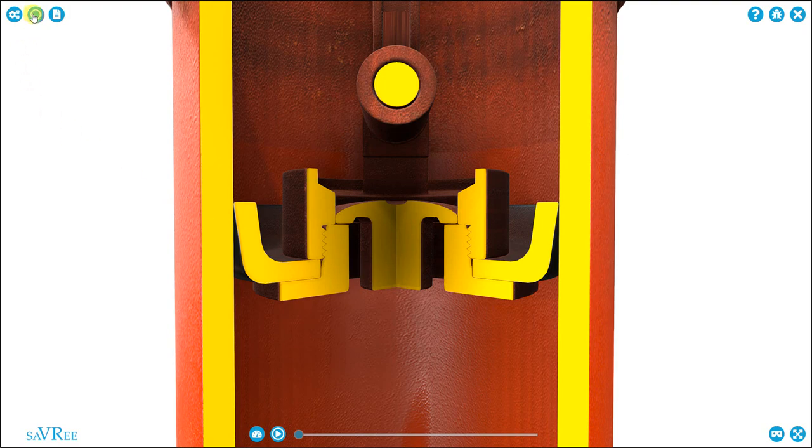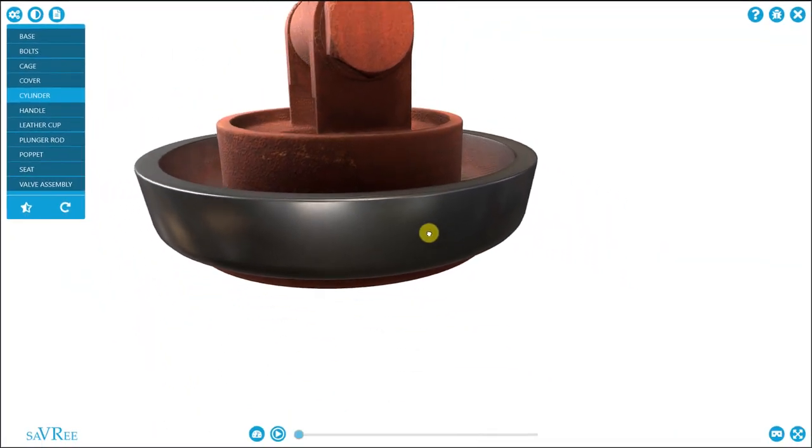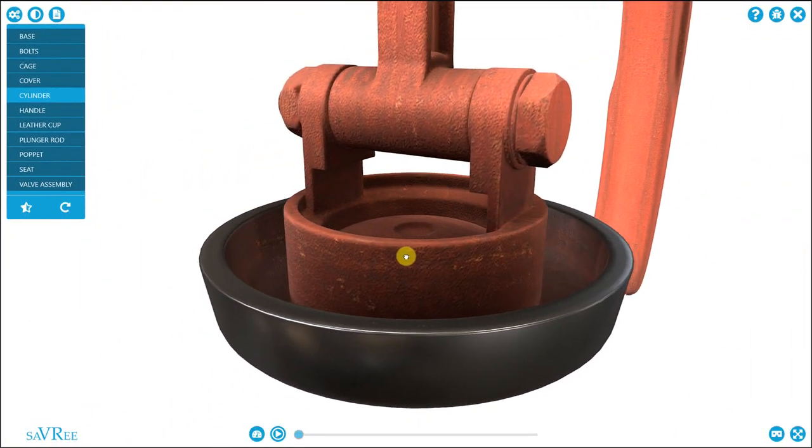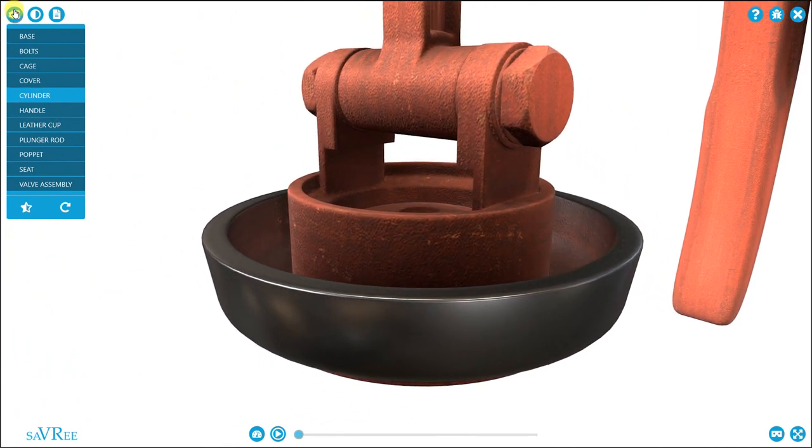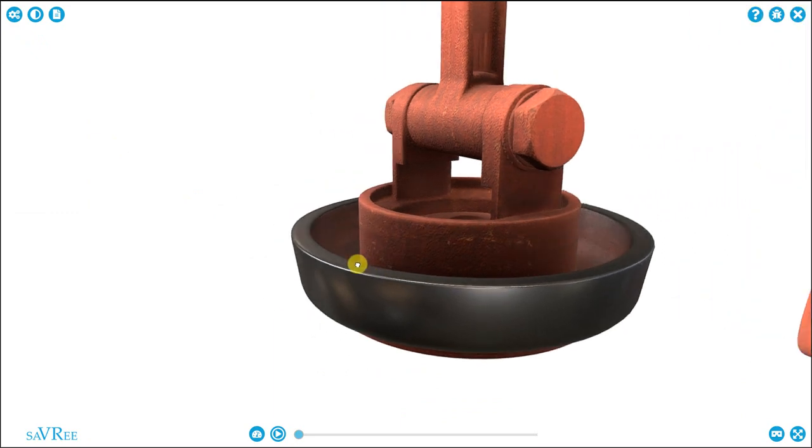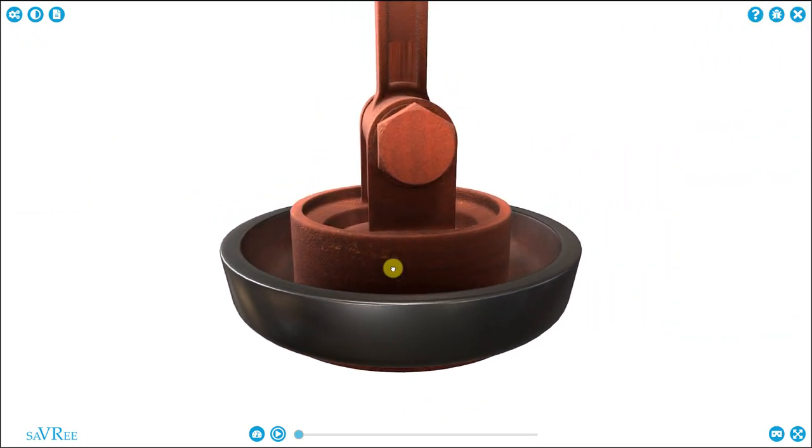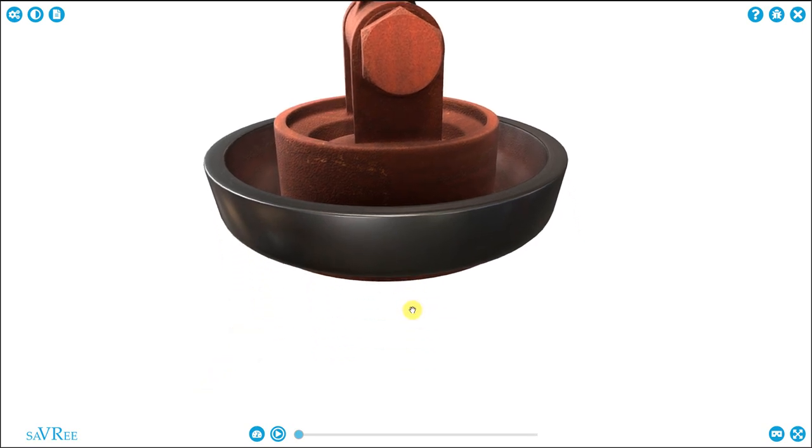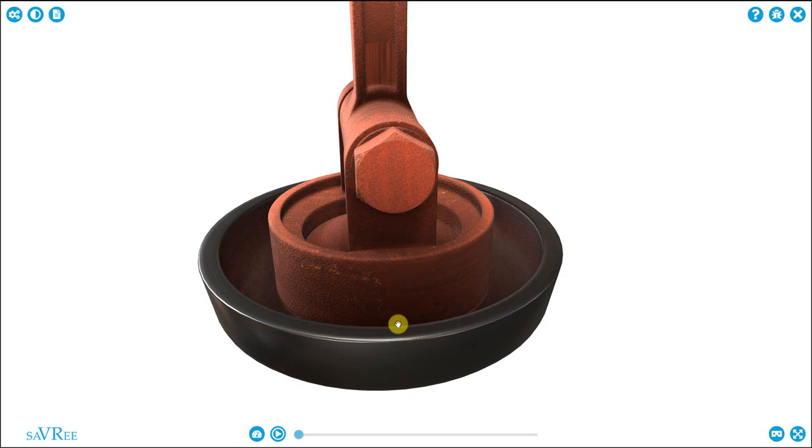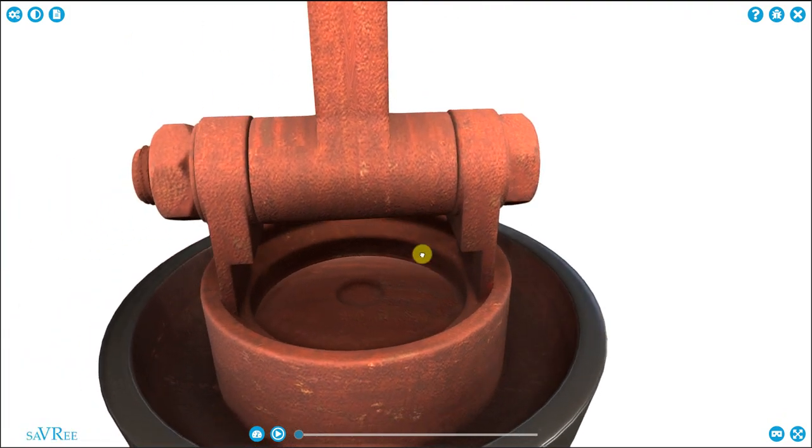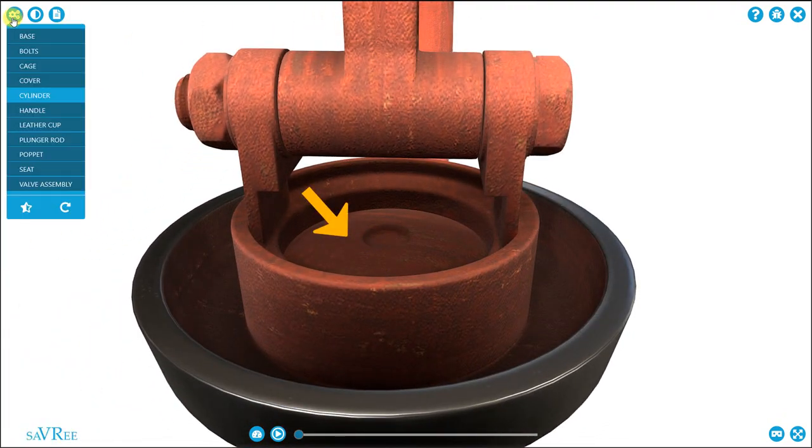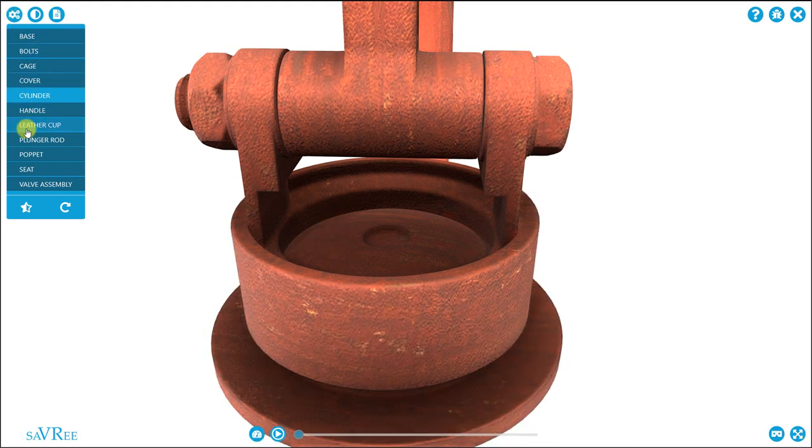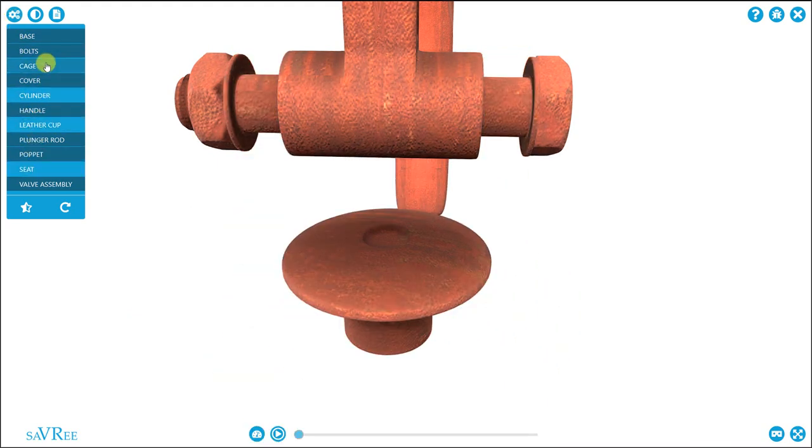Let's go back to full screen mode for a moment. And then what we'll do, we'll take the cylinder away and we can have a look at the part in a bit more detail. We've actually got a sealing arrangement or a sealing item around the piston assembly. I'm just going to say piston from now on because it's a little bit quicker. This item here, the black gray item, is usually a piece of leather called a leather cup or a similar kind of material that's used to seal the space between the piston and the cylinder. We have a non-return valve located here. What I'll do, I'll take away some parts so we can see it. I'll take away our leather cup, take away our seat, and I'll take away our cage.